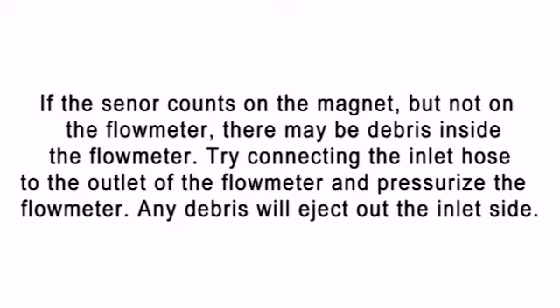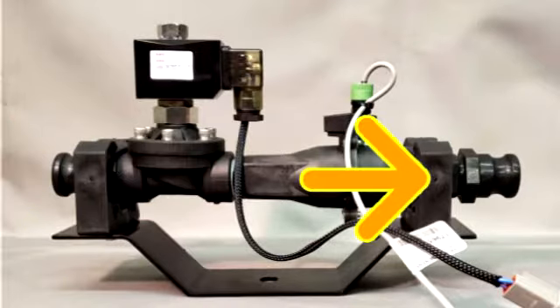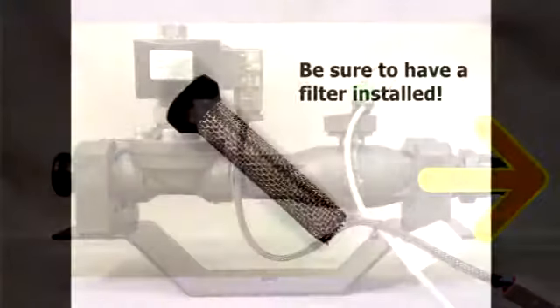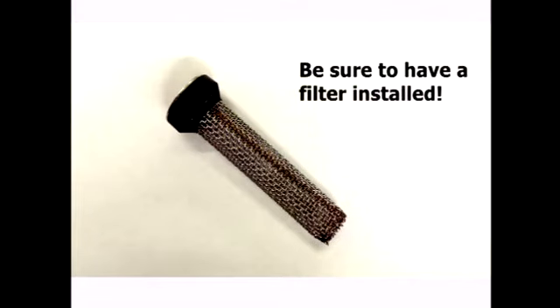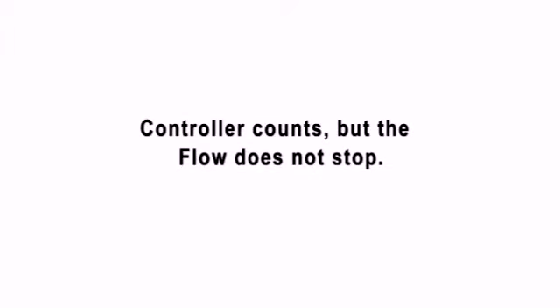If the flow sensor is counting on the magnet but not the flow meter, there may be debris inside. So let's try connecting the inlet hose to the outlet and pressurize it - this will eject anything from the inside. Also make sure you have a filter installed on the inlet side to keep debris out.